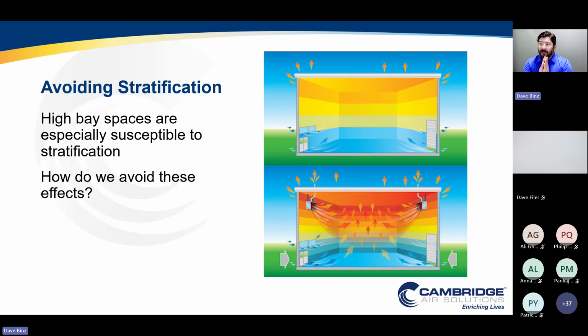But how about the system side? In industrial retrofits, where we're trying to balance indoor air quality and temperature distribution with energy costs, the biggest driver of energy challenges in warehousing is stratification. I want that heat at the floor, but the heat rises due to the low density of hot air. In many applications we've seen 15, maybe even 20 degrees of stratification. If I'm controlling at 65 degrees at the floor, it could be 85 degrees at the ceiling. That creates a lot of excess energy. Now my mixed air temperature is almost 75 degrees, so I'm heating that building 10 degrees warmer than it needs to be. And that stratification induces more infiltration, so my infiltration rate could potentially double because my stratification is so poor.